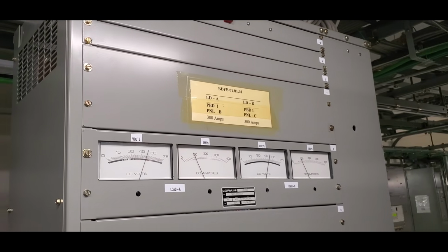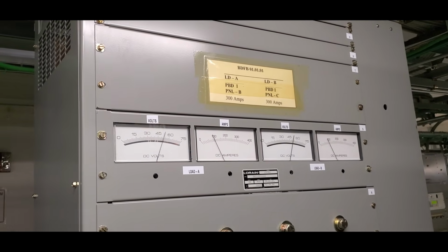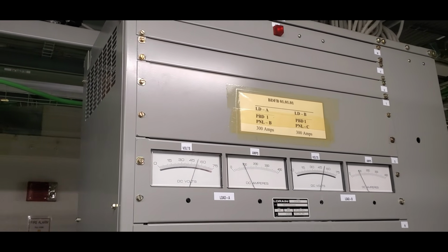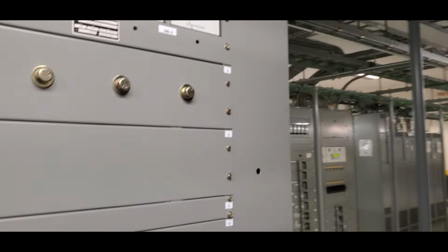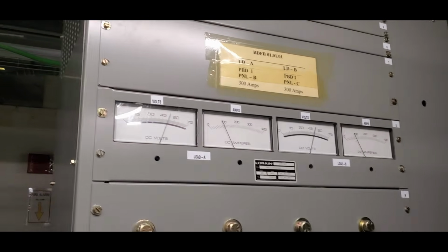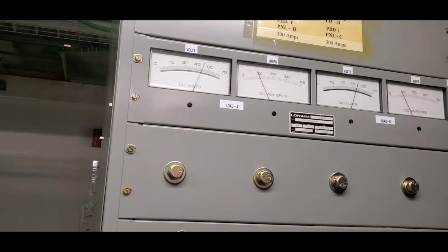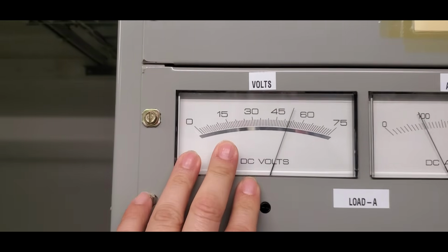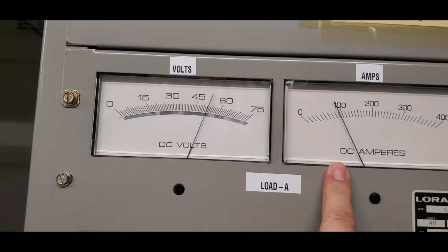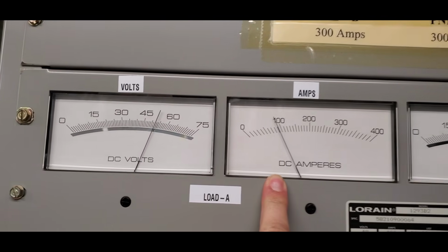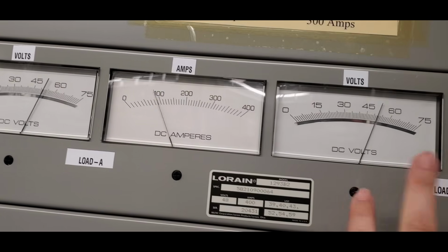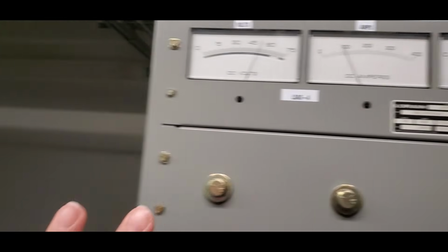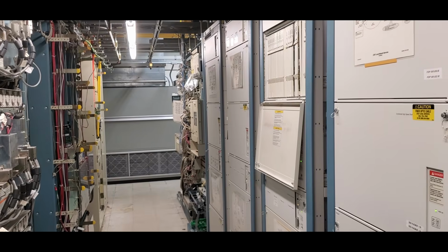So now we come down to the actual distribution circuit panel. And this is taking the power from one of those circuit breakers that we've seen over there, and now sending it to the individual equipment. So for example, this bay right here shows us supplying the 52 volts, about 90 amps of current, and this is one of the other loads here. And all this panel does here is supply maybe just this bay down here.